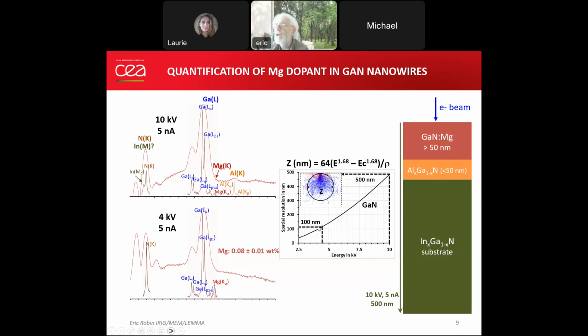So it would be possible to continue to vary the voltage, increasing it slowly to see when the aluminum peak appears, when the indium peak appears, and so we are able to determine the approximately exact thickness of this layer and this layer. And it's also possible now to measure the magnesium concentration from this peak here, which is about 0.08 weight percent. So we are able to measure some dopants, and we did that for dopants like silicon, phosphorus, and different dopants in different lines.